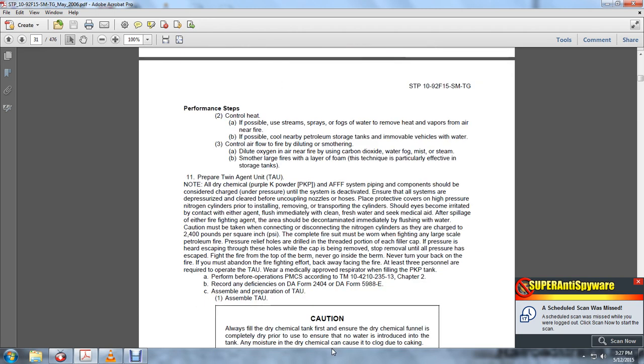Prepare a twin agent unit. Note: all dry chemical, purple K compound, PKP, and AFFF system piping and components should be considered charged under pressure until the system is deactivated. Ensure that all systems are depressurized before uncoupling the nozzles or hoses. Place protective covers on the high pressure nitrogen cylinders when installing, removing, and transporting the cylinders.